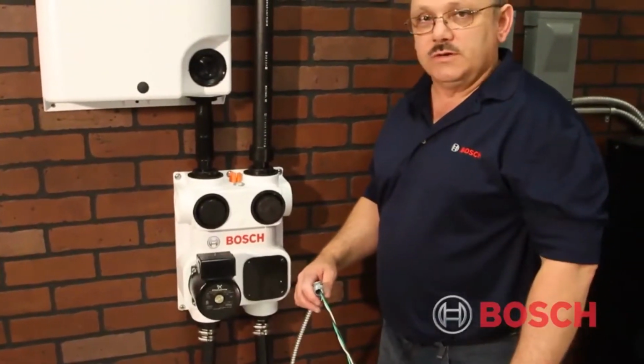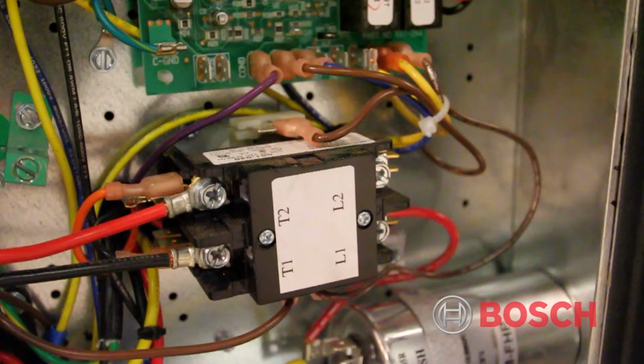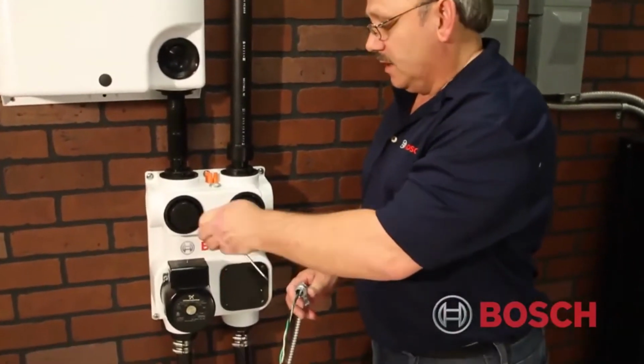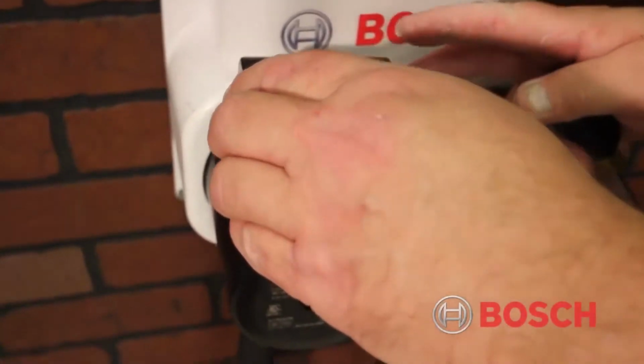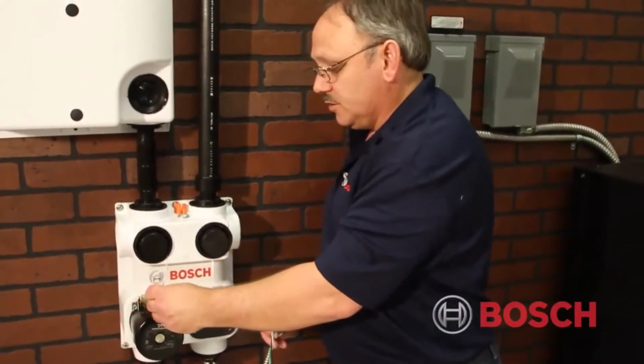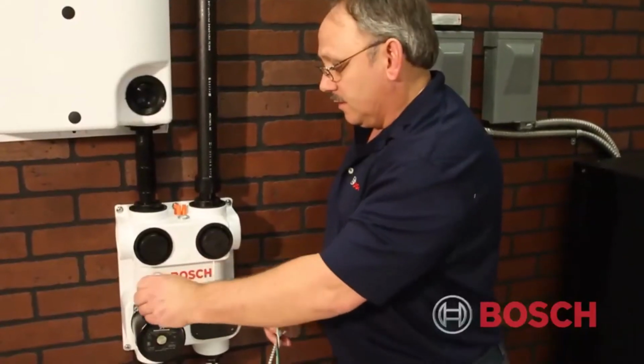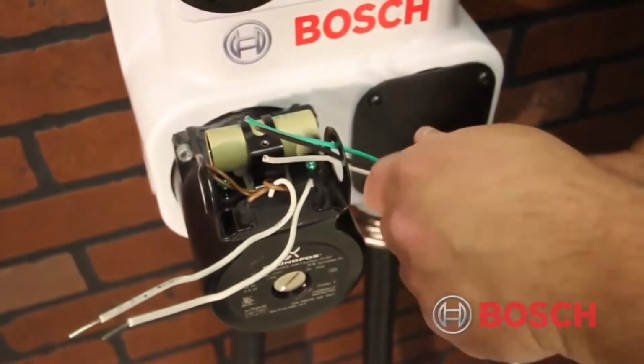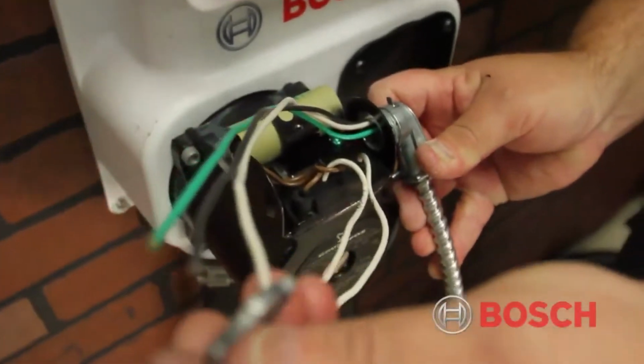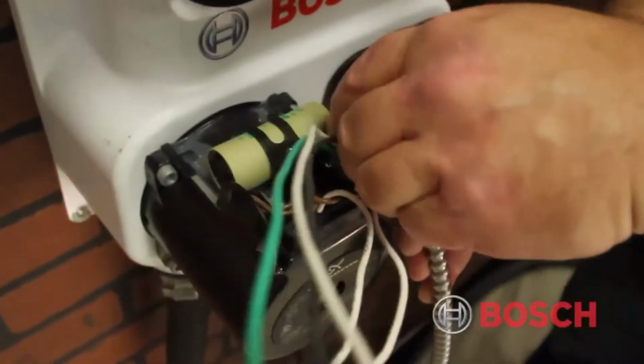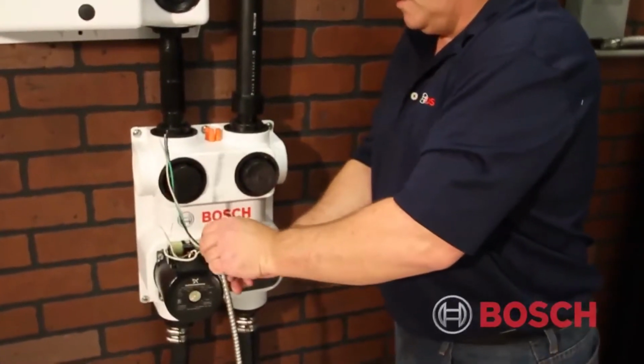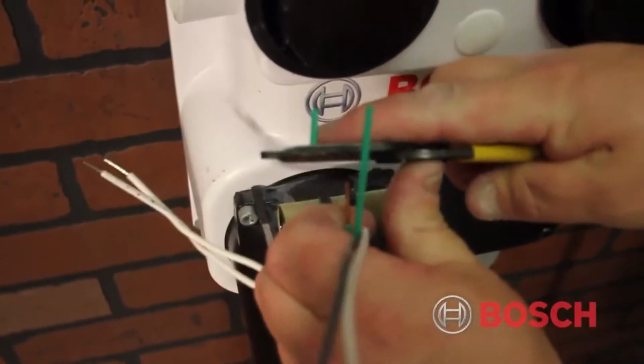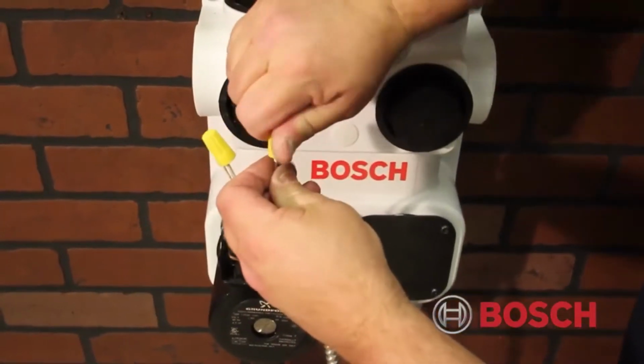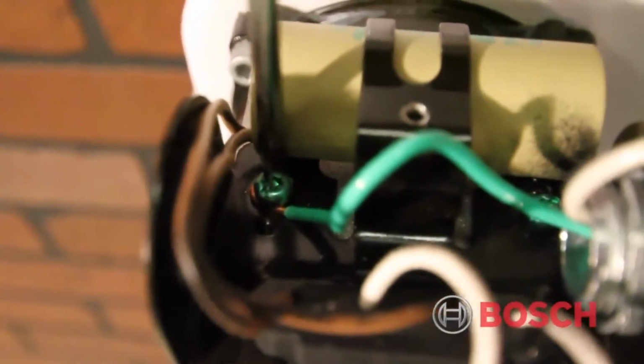Next, we're going to make our electrical connection to our circulating pump. This is our wire coming from our unit that is wired into the compressor contactor to terminals T1 and T2. This is the electrical box on top of the pump. You simply remove the screw on the electrical box and remove the cover. There are 2 wires to make your connection to. There's also a grounding screw back behind the capacitor. Now you just insert your wire through the electrical knockout on either side of the pump housing. There's an additional knockout on the other side.